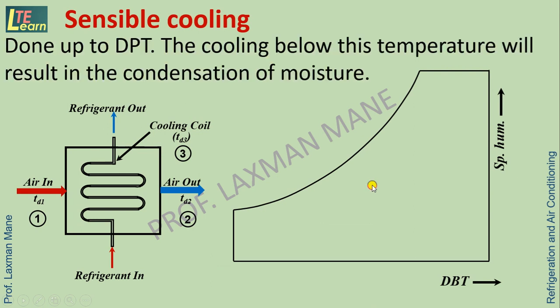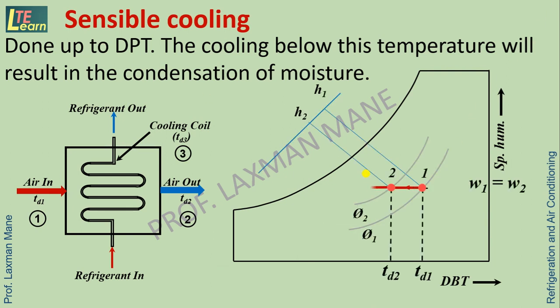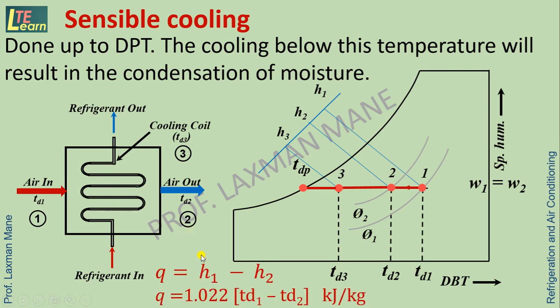In sensible cooling, the air is cooled down to its dew point temperature. If the air is cooled below the dew point temperature, condensation of moisture will take place and the condition of air will fall outside the saturation curve. Air passes over a cooling coil through which refrigerant is passed. The amount of heat removed from the air is given by Q = H1 − H2, where H2 is the enthalpy of the outlet air (kJ/kg).